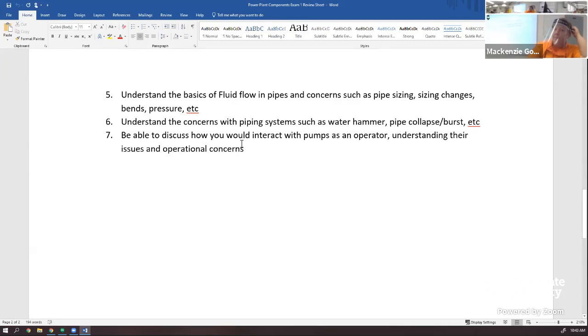Yeah, Sam. Water hammer is like you shut off the valve really quick. Right. So you got your velocity going forward, then all of a sudden you shut this really fast and it hits the solid wall and it bounces back. And all that energy translates back into the pipe. And you get vibration and potential valve and pipe damage. And the same thing can happen with steam hammer.